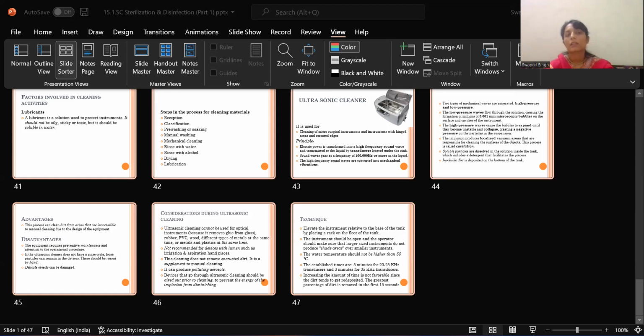Now, for the sterilization time, autoclave at 115 degrees Celsius at 10 pounds per square inch, it can be kept for 45 minutes, whereas for 121 degrees Celsius at 15 pounds per square inch for 15 to 20 minutes, at 134 degrees Celsius at 30 pounds per square inch for 3 minutes. For flash sterilization, which can be done for emergency situations, can be done at 132 degrees Celsius at 30 pounds of pressure for 3 minutes.